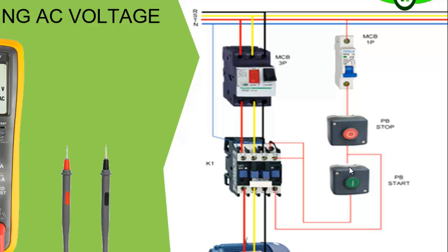Okay, which means that at the input to your start button, which is a normally open push button, we have voltage signal. So if you do not have an output from this normally closed stop push button, it shows that this push button is bad, or there is a problem with it. It's possible that there are build-ups, debris, okay, on the contact. Increased resistance can also insulate the contact. Okay, so you can zero in on the stop push button for further checks to ascertain what is actually wrong with the push button. So next is the start push button.